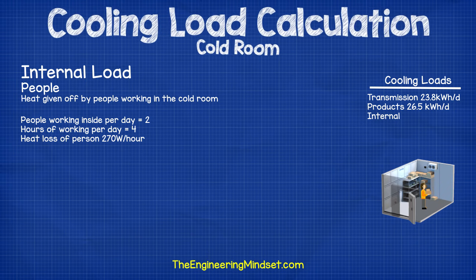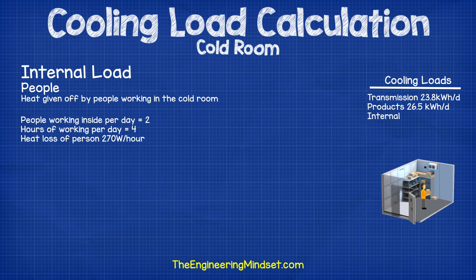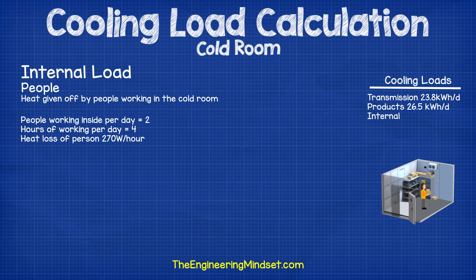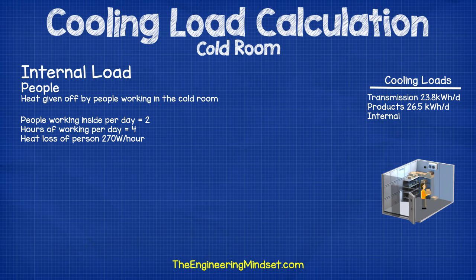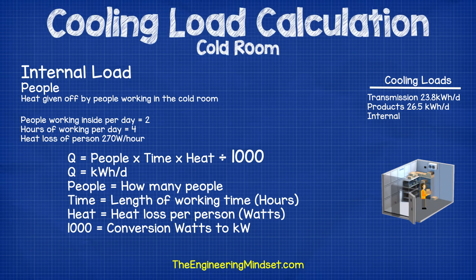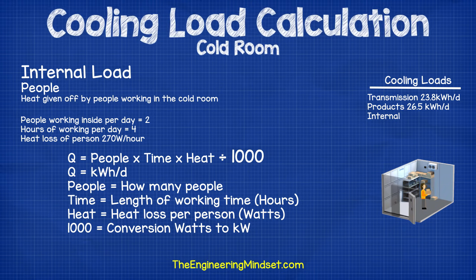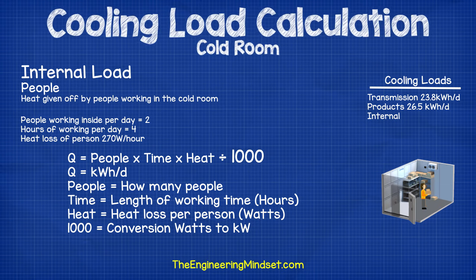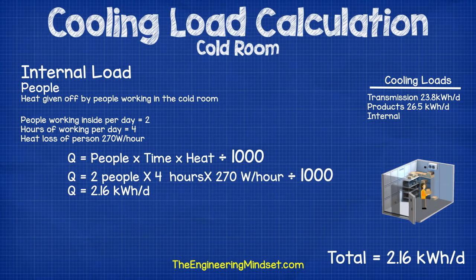Next we'll calculate the internal load from people working in the cold room, as people generate heat and we need to account for this. We'll estimate two people working in the store for four hours a day; at this temperature they will give off around 270 watts of heat per hour inside. Using the formula q equals people multiplied by time multiplied by heat divided by 1000, where 1000 converts watts to kilowatts, dropping those numbers in gives us 2.16 kilowatt hours per day.